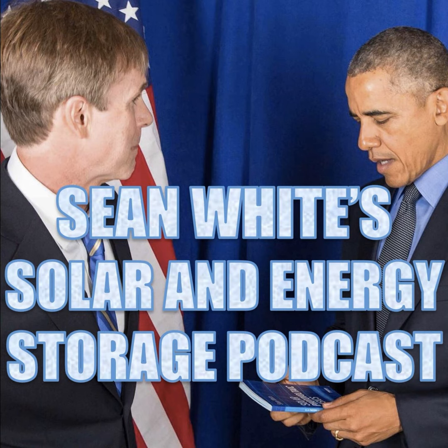It is very short. It is 705.13, and it is a very important new thing in the National Electrical Code. So I'm just going to read this. 705.13 Power Control Systems. Power control systems, PCS, shall be listed and evaluated to control the output of one or more power production sources, energy storage systems, and other equipment. The power control system shall limit current and loading on the bus bars and conductors supplied by the power control system.